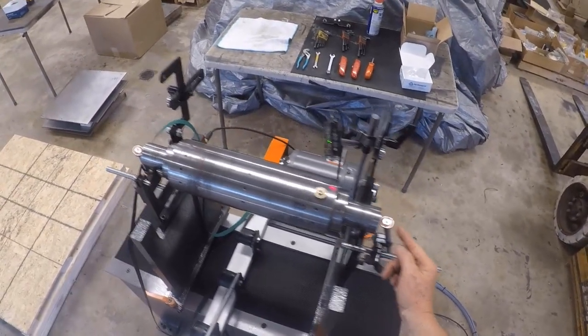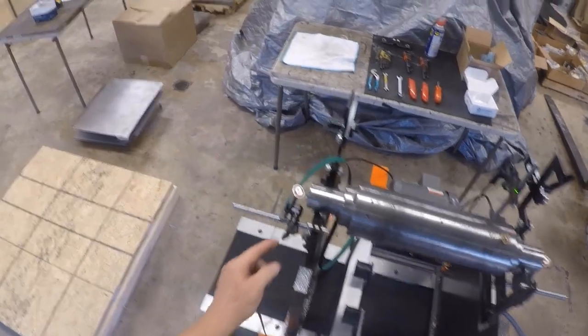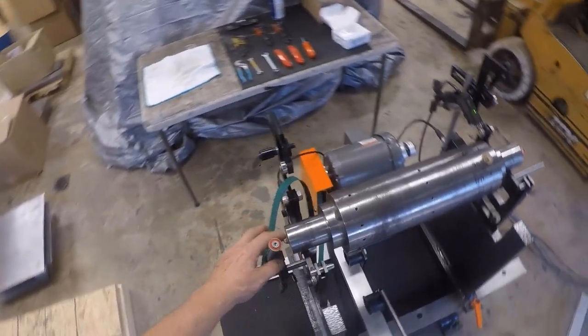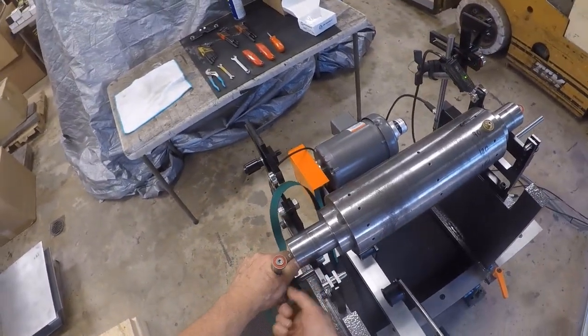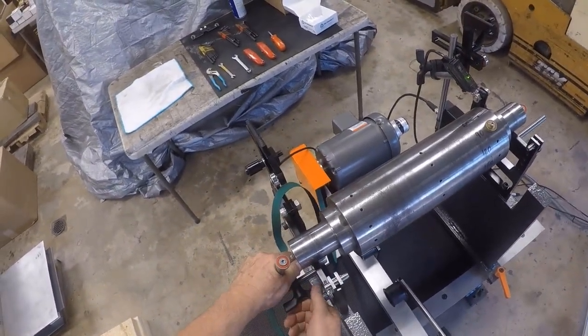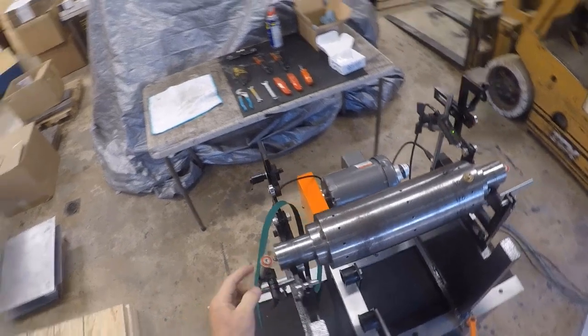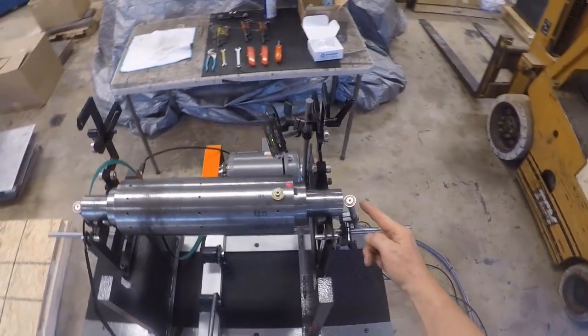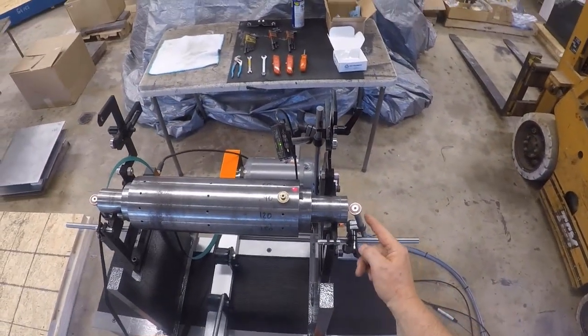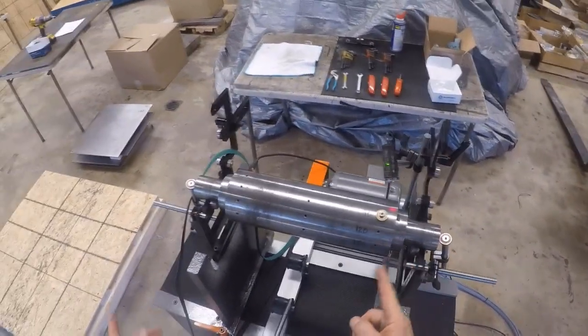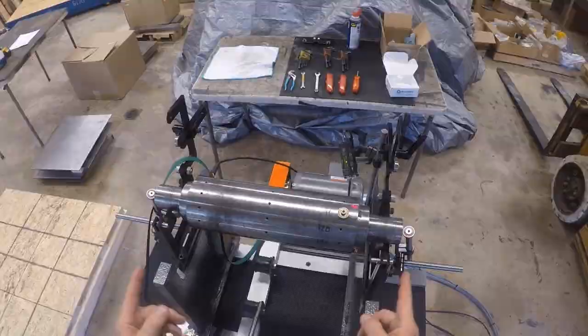Next we adjust our end thrusts. That is very important—the rotor is not allowed to move left or right. We need to adjust these so that only one bearing at a time can touch the rotor, so the rotor is contained but not constrained.